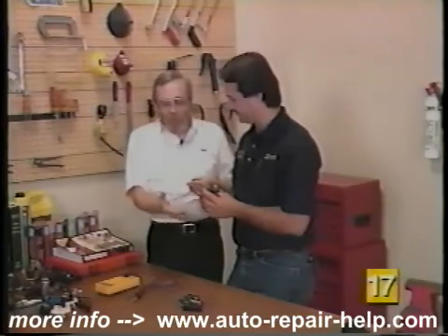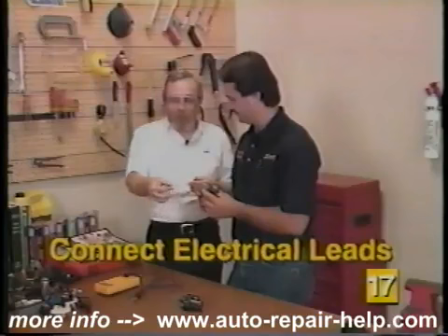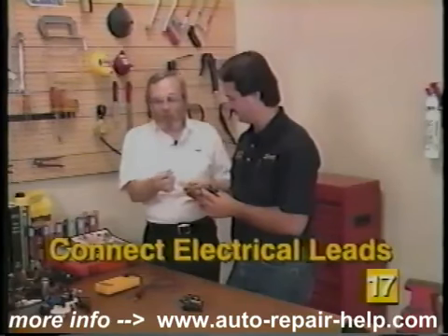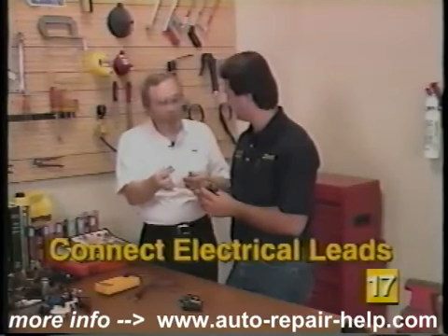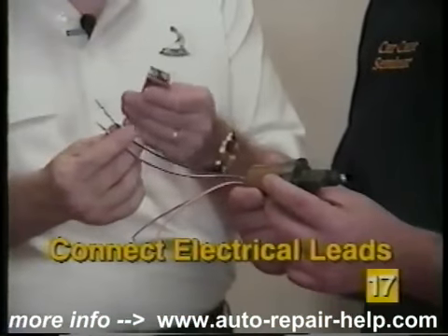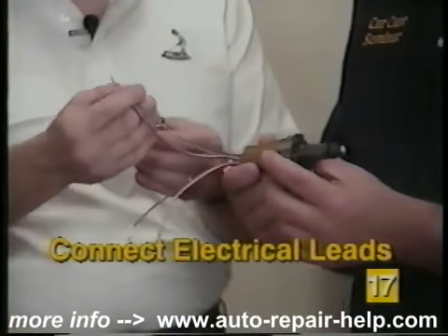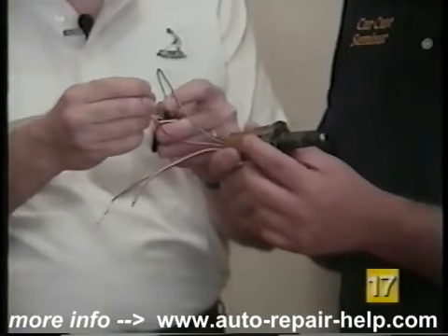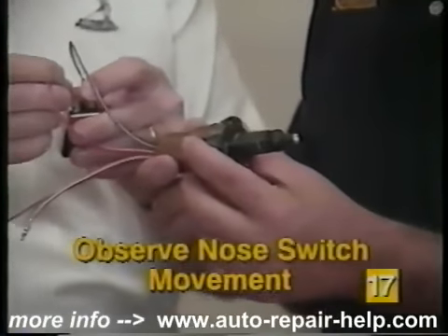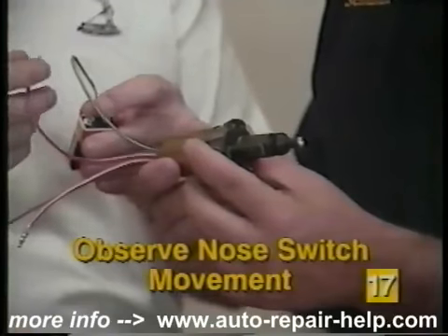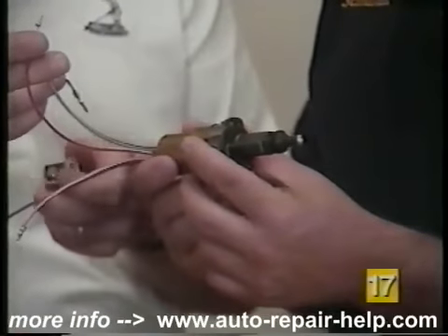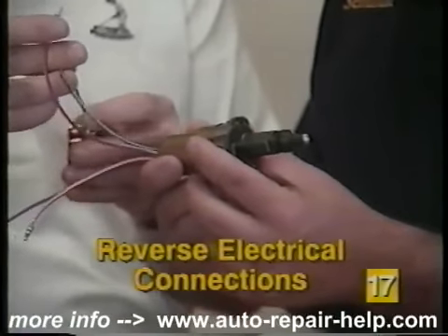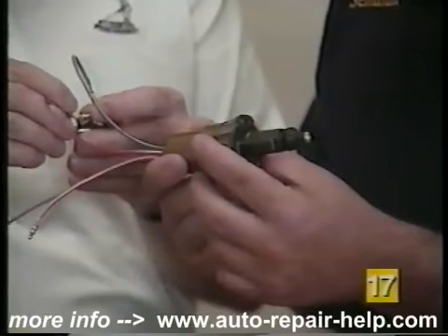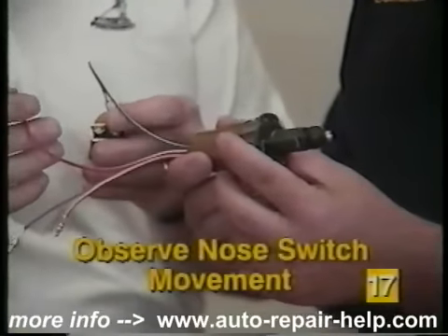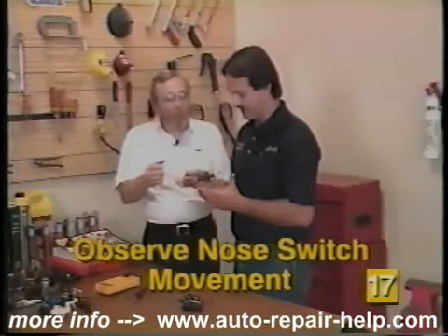To test, you need to find the red and the black wires, which traditionally mean positive and negative in electronics, and connect those to your battery terminals. So as I connect the black lead to the negative battery terminal and the red one to the positive, it should extend the nose. And as you can see, it did that. And to retract it, we simply reverse the connections on the battery, and it should move in the opposite direction. And it did, without any binding.